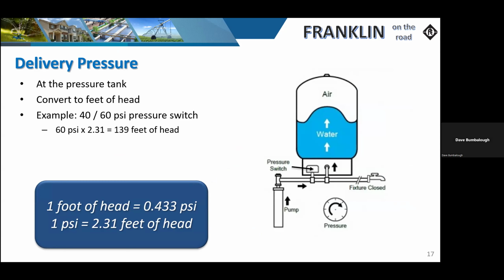So first thing we want to look at is delivery pressure. Sometimes we may have it on a pressure switch. We may have some kind of sensor, such as a transducer, or some other means of monitoring what that line pressure is. Well, we have to convert that. So as you look at, say, a standard pressure switch, say we installed a 40-60 pressure switch, we're looking at the bigger number. The bigger number is what shuts that system off. So our pump and motor has to be able to develop enough pressure to satisfy that switch to turn it off. Otherwise, we get a run-on situation.